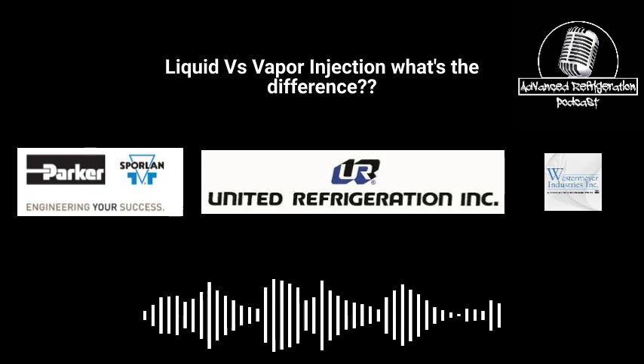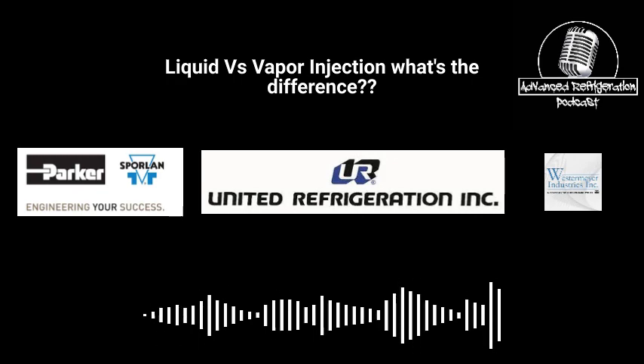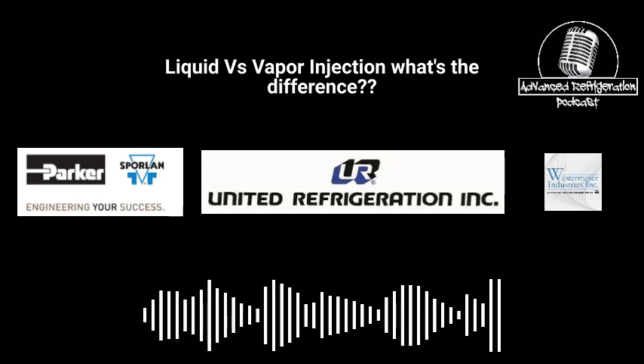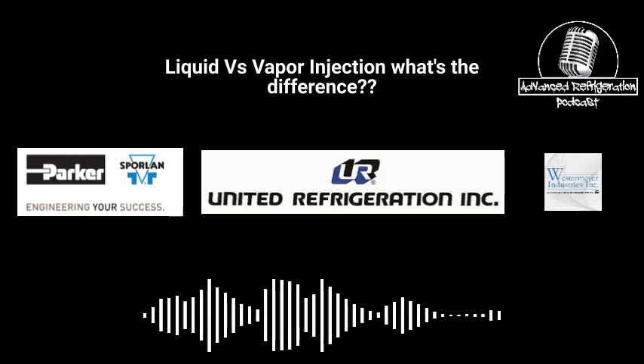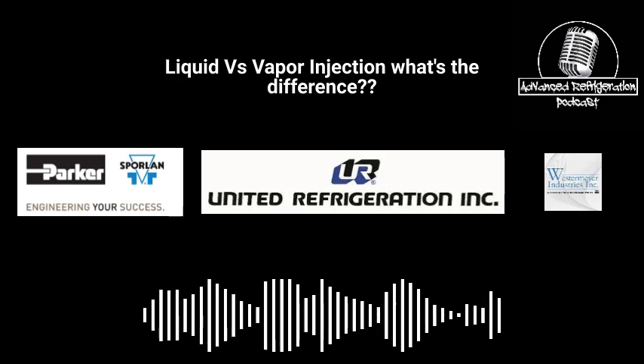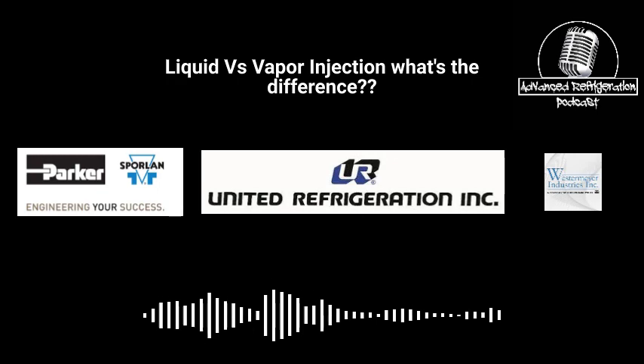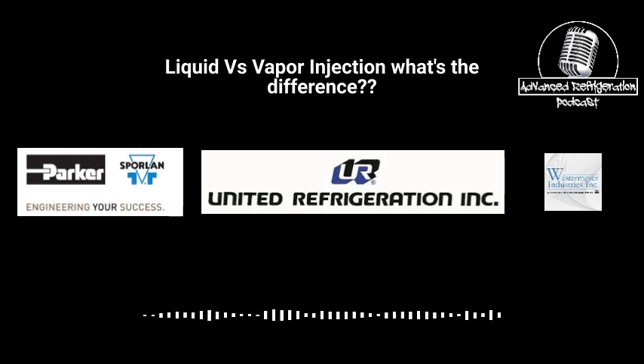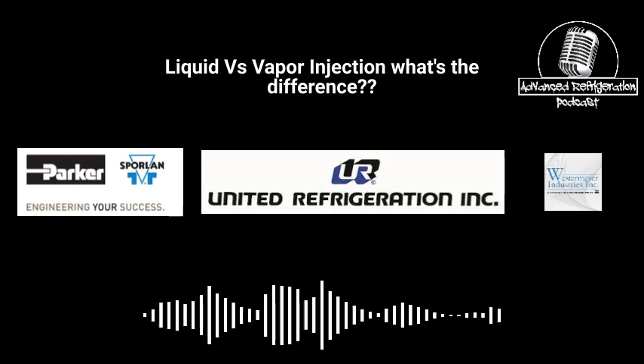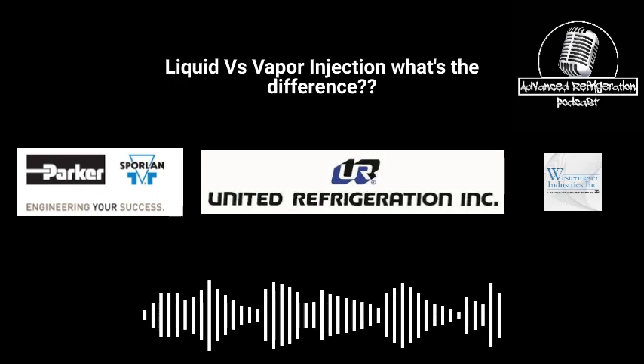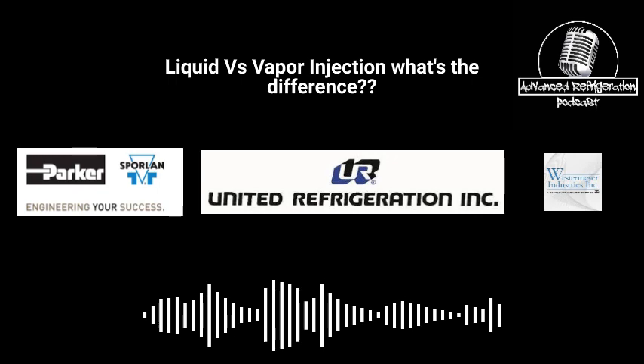It's not like you're saving a bunch of energy, but you're not using more energy like you would with liquid injection. See, liquid injection is you're just paying for nothing. You're paying just to cool the compressors. Now you're paying to cool the compressor and you're getting subcooling, which is going to make the rack larger, everything more efficient, make it run smoother.